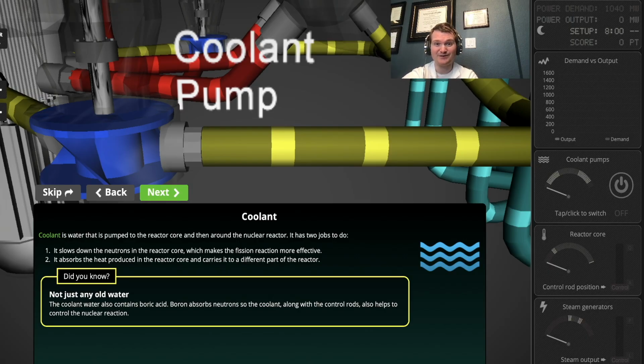Yes, you would not have a fission reaction during a loss of coolant accident. You lose the coolant, the reactor's shut down because nothing's slowing down those neutrons, meaning they're not going to fission. That is one thing you don't have to worry about, is shutting down the reactor when you lose the coolant. When you do, you activate your emergency core cooling system to keep the shutdown reactor cooled.